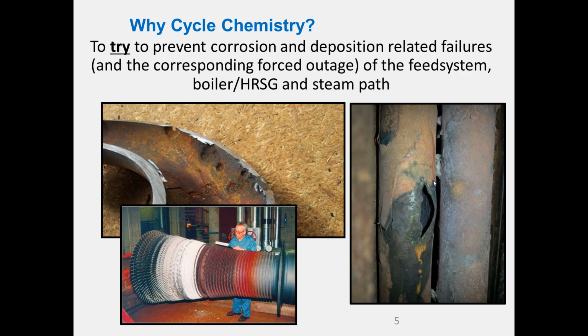Here's what we call a short-term overheating failure in another plant, and this is a multicolored turbine because some of the chemical components in the feed water have ended up on a turbine, and it's not really great because it significantly impacts on the performance of a steam turbine.